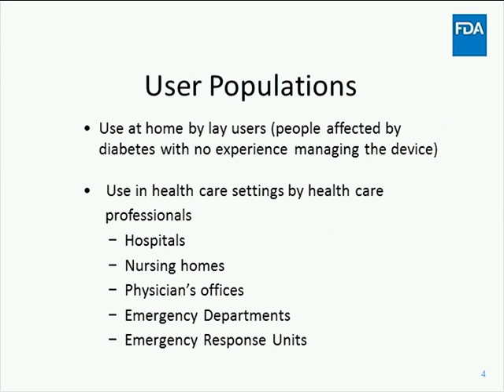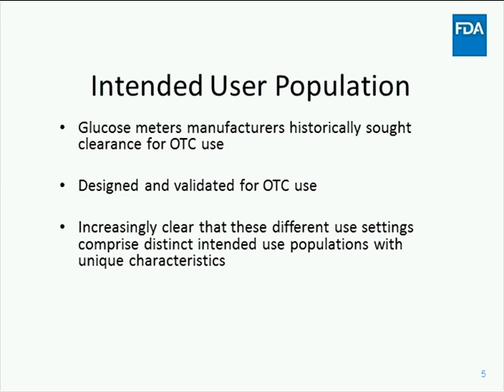Blood glucose meters are used by very different and unique intended user populations in a variety of settings. They are used by lay users at home. Also, they are used in a variety of healthcare settings, such as hospitals, nursing homes, doctors' offices, among other settings. And as you may know, blood glucose monitoring systems are considered moderate risk and are therefore Class 2 devices that require 510K clearance prior to marketing. During the 510K review, we evaluate the performance of the device for its intended use. However, this is not an independent evaluation of the device. Manufacturers are responsible for the demonstration of the performance. Therefore, the device information and performance data that we evaluate is generated and provided by the manufacturer.